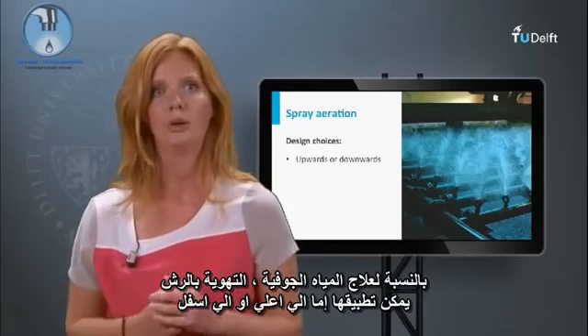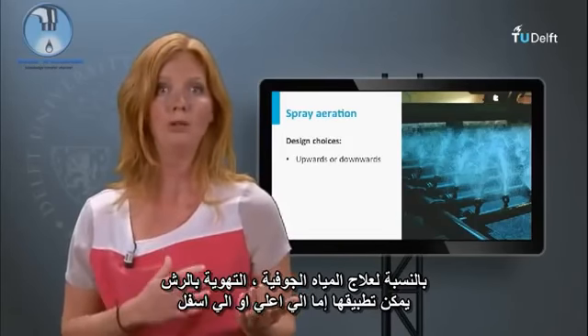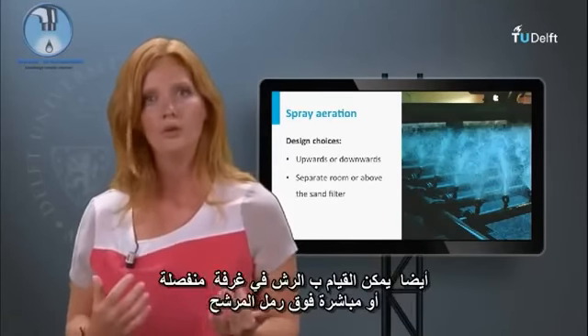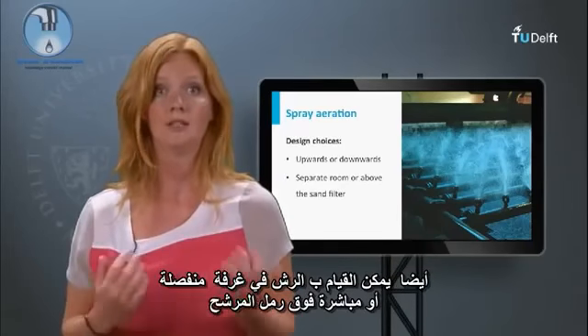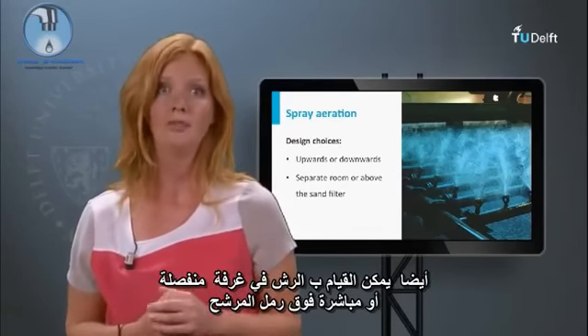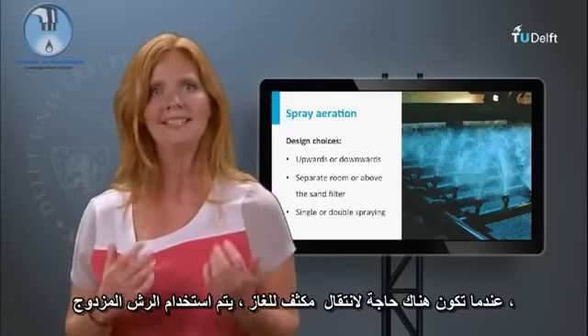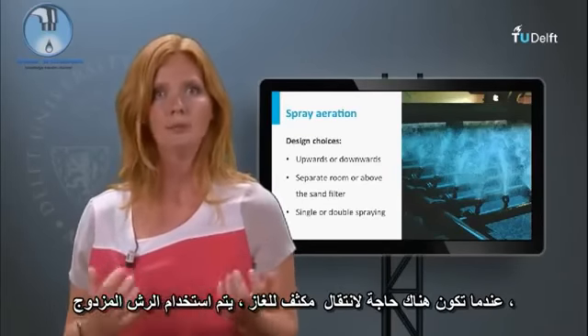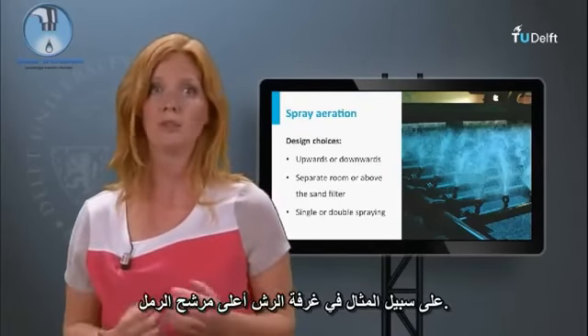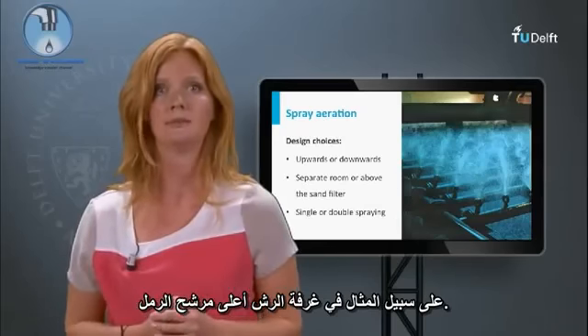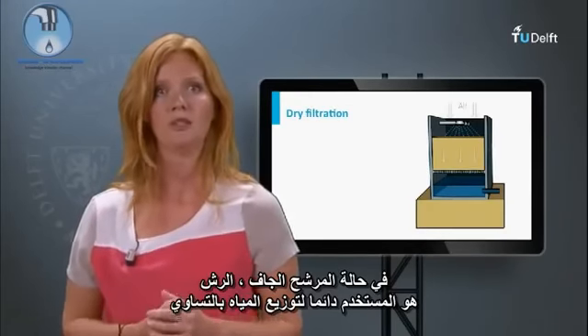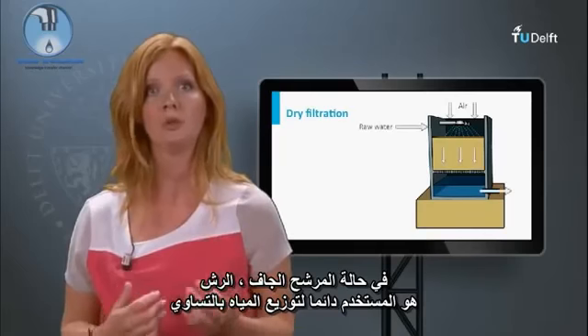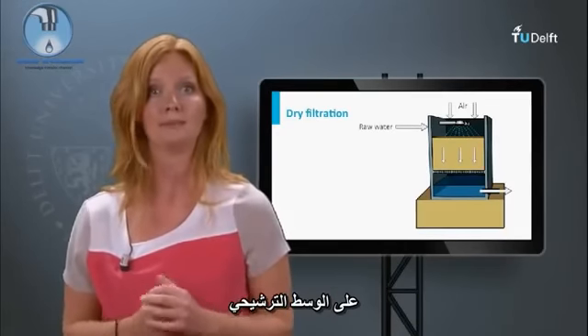For the treatment of groundwater, spraying can be applied either upwards or downwards. Also, the spraying can be done in a separate room or directly above the sand filter. When intensive gas transfer is needed, double spraying is employed, for example with the spraying room above a sand filter. In the case of dry filtration, spraying is always used to distribute the water evenly over the filter bed.